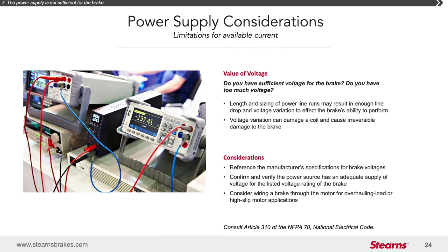Improper voltage to the brake can cause several issues which can ultimately destroy the brake. If the brake does not receive enough voltage, this can not only hinder the release of the brake, but can also cause the brake coil to overheat and fail in the example of an AC brake. Too much voltage can also be a problem, as it can cause the brake coil to rapidly overheat and fail. Another problem could be unregulated power or dirty power. If a system is powered by a generator without the protection of a transformer, this can cause voltage spikes and/or brownouts, which can destroy a brake coil and ultimately destroy your brake.